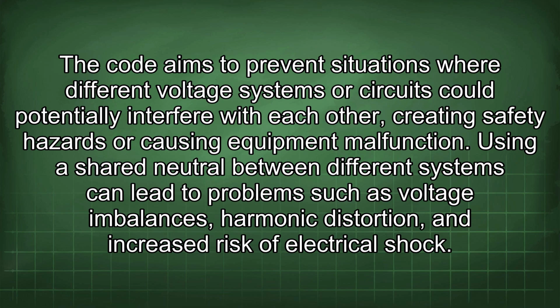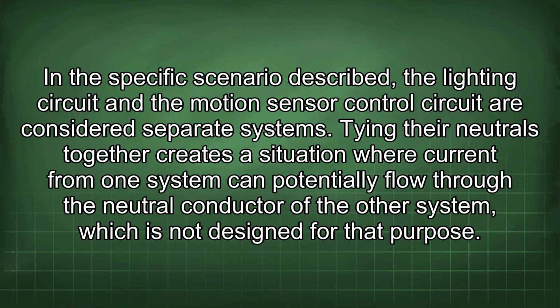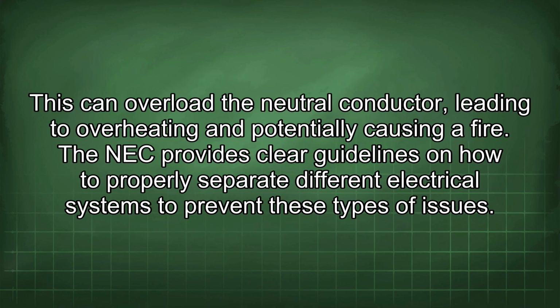In the specific scenario described, the lighting circuit and the motion sensor control circuit are considered separate systems. Tying their neutrals together creates a situation where current from one system can potentially flow through the neutral conductor of the other system, which is not designed for that purpose. This can overload the neutral conductor, leading to overheating and potentially causing a fire. The NEC provides clear guidelines on how to properly separate different electrical systems to prevent these types of issues.